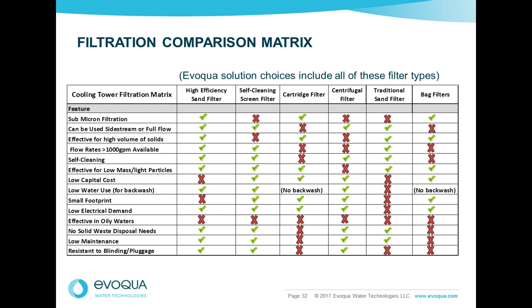I remember one specifically, the maintenance guy was telling me that he's more worried about repairing pumps and seals and packing. He didn't have time to deal with a cartridge, so he kept putting it off and putting it off. Eventually they just bypassed it, and that usually is what happens. You just don't have maintenance crews that want to deal with changing these cartridges out, so they end up bypassing them or isolating them. So they may not be a great choice for you depending on your situation.